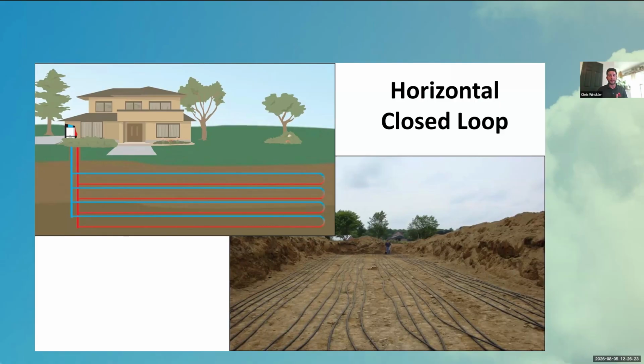There's also more heat in air conditioning because we have to get rid of the heat created by the compressor into the water, whereas when heating a house, that heat generated by the compressor is actually a benefit. So without getting into too much detail, it's easier to design a system with simultaneous heating and cooling on a large scale than in a small residence. It just gives us an easier way to hit higher water temperatures.